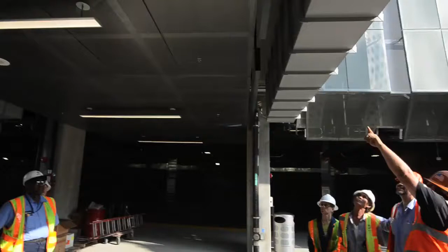These LED lights here all have remote drivers. And because this ceiling's not really your typical accessible ceiling, what we did is we installed all the drivers on the end here, so those are those silver boxes. So if that light went out, what you need to do is get up here and open up that driver, check your incoming power, 277 volt, and then check your output.